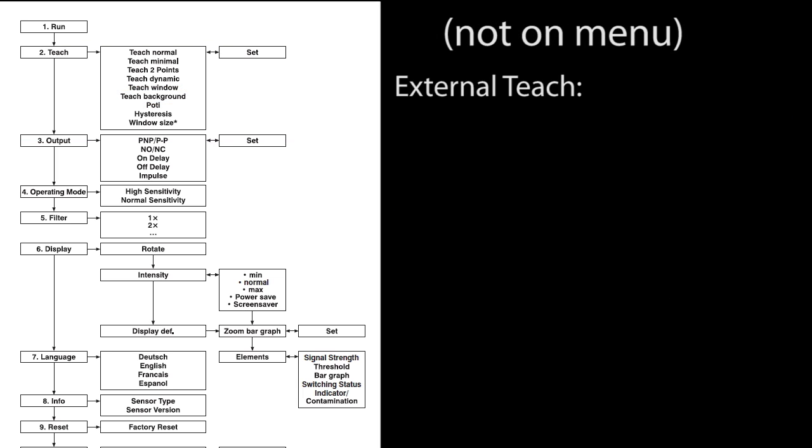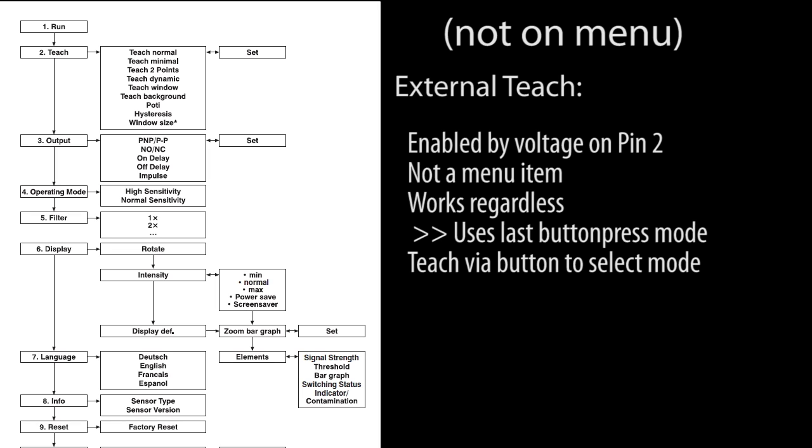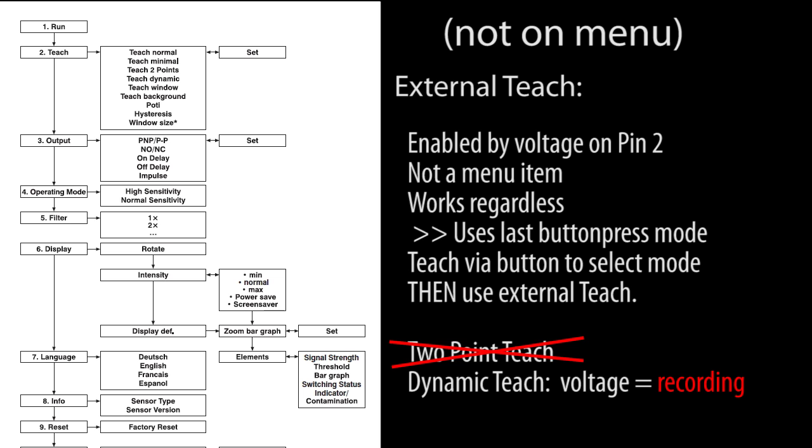External teach does the same thing as we just did but instead of pressing buttons to select thresholds you apply 10 to 30 volts to pin 2. External teach isn't a menu item. When that voltage is applied to the sensor it will reteach a detection threshold as if the sensor was in whatever mode you last taught. So you have to teach a mode via button presses first and then you'll be able to use external teach. Also, you can't do two point teach via external teach and dynamic teach teaches as long as the voltage is applied.